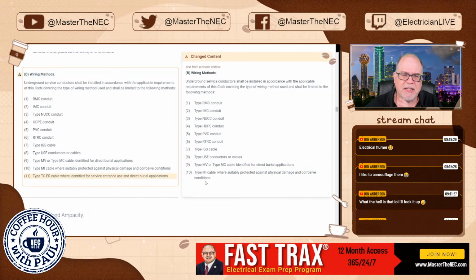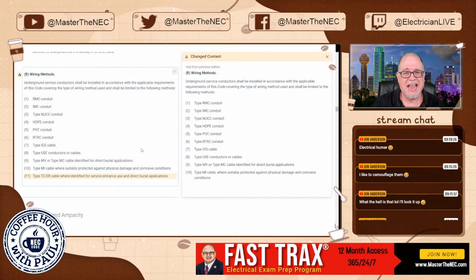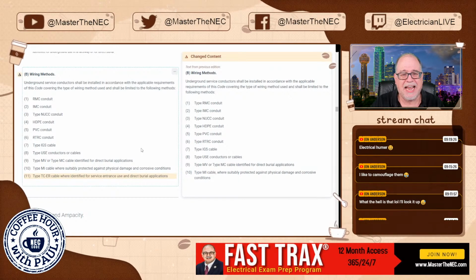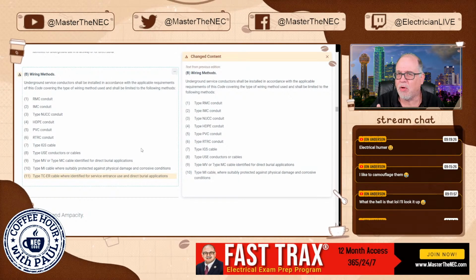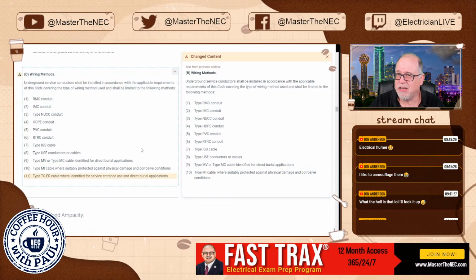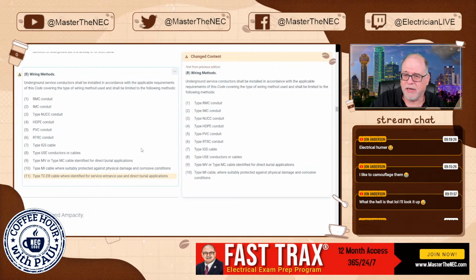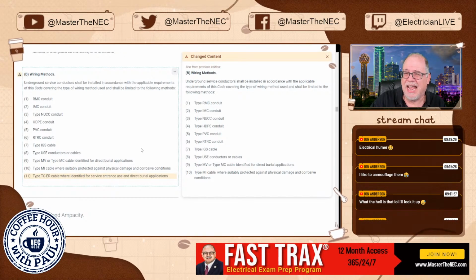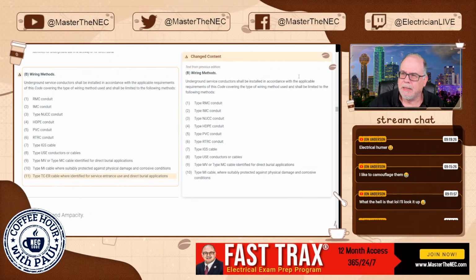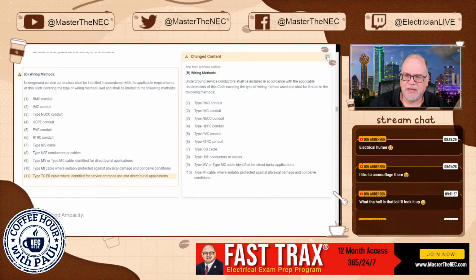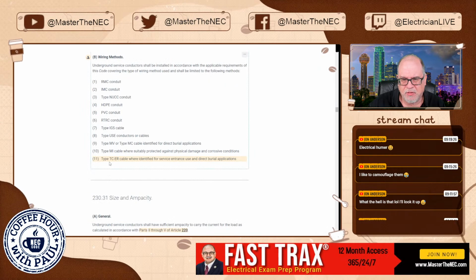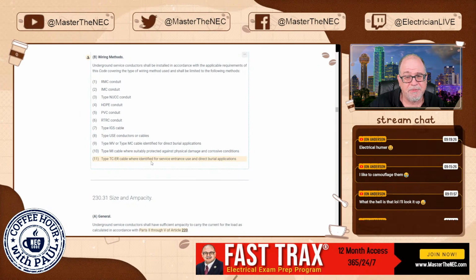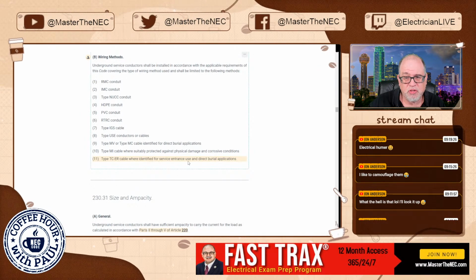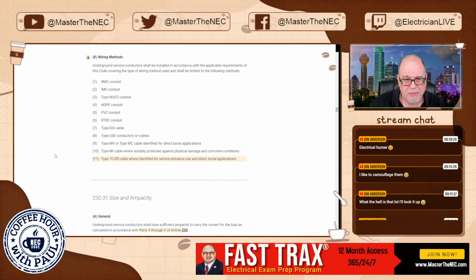Now, the significance of this change is that it adds TCER for underground service conductors. We know that a lot of tray cable is rated for direct burial, for underground. So this made sense to add here, okay? Now, one of the other significant things to remember is that it says TCER cable identified for service entrance use and direct burial applications.